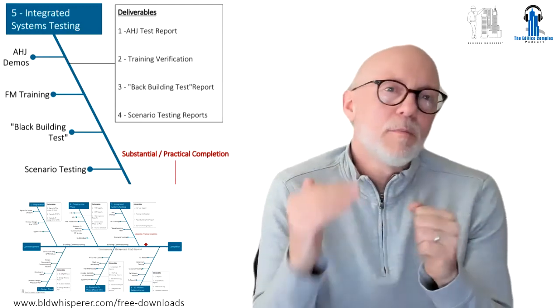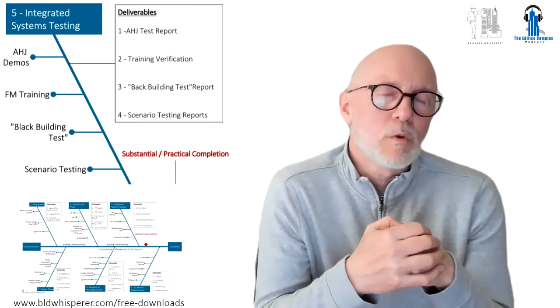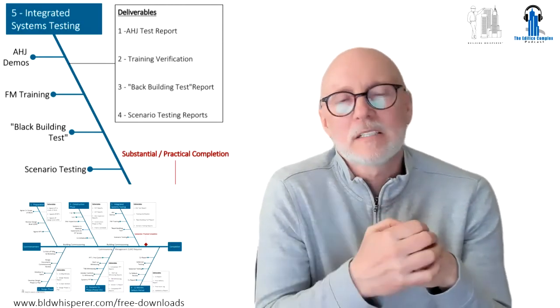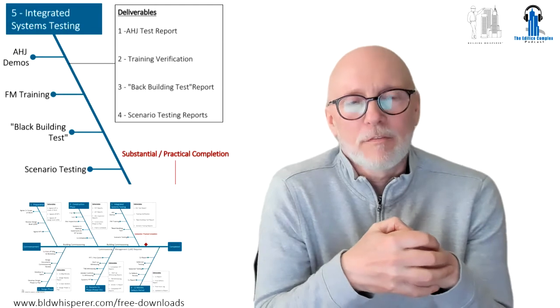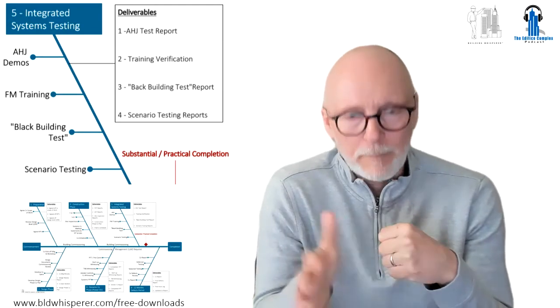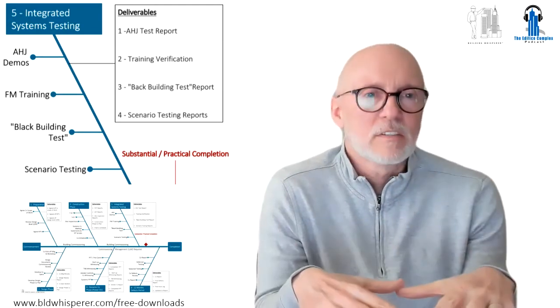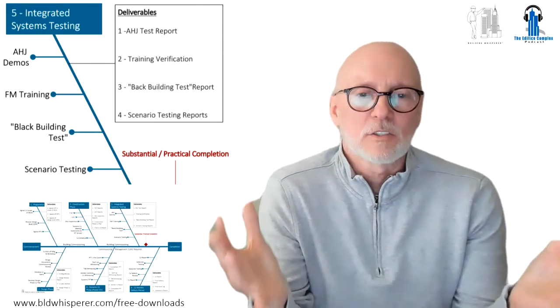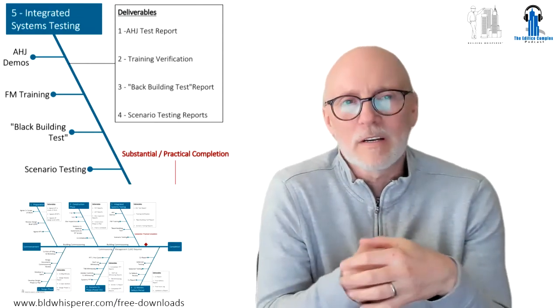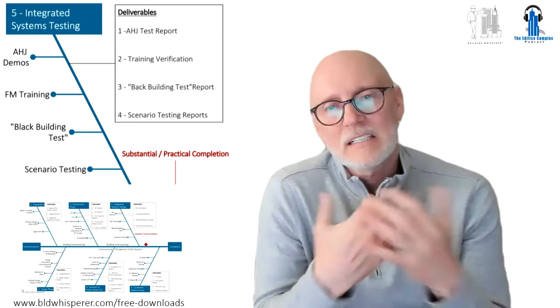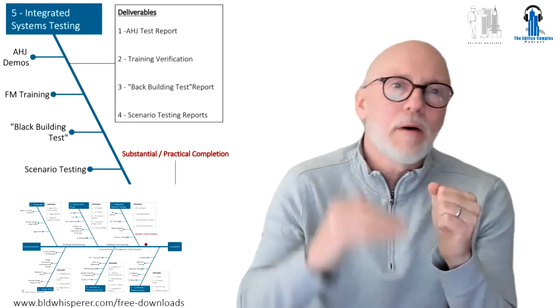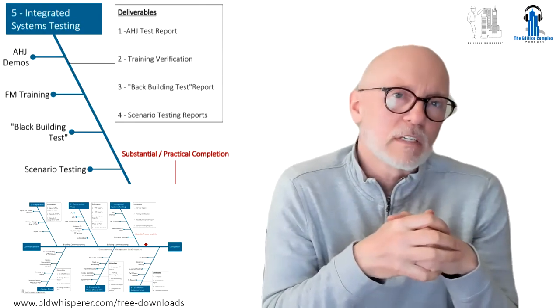The next level up from that is black building testing. So on top of the bare basic you add a power failure test - you fail the power, do the systems go down as they should, and do they come back automatically as they should? That's a half-day to one-day test that should be done. For me that's a bare basic, but it's a step up from what the authority having jurisdiction requires.